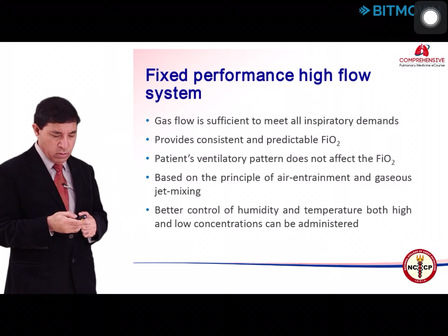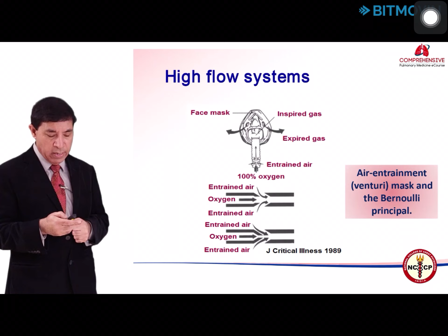The heart of the high flow system is a Venturi device, as you can see here, where the oxygen is passed through this narrow tube and exits from a narrowing. When this oxygen exits from the narrowing, it comes out as a jet. It creates a negative pressure around it, which results in the entrainment of air. So, depending upon the flow rates and the size of this port, the negative pressure will be generated and there will be an entrainment of air. By adjusting the flow rates and the port size, you can create a ratio of oxygen and entrainment, which you can also calculate by a magic box.